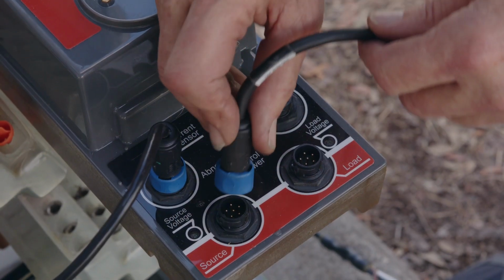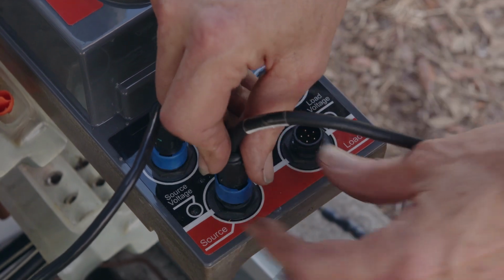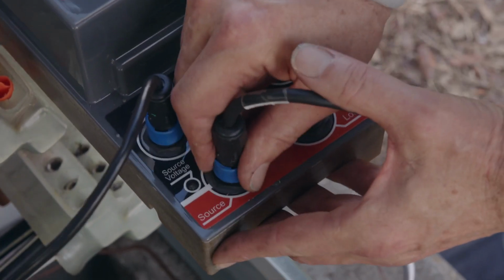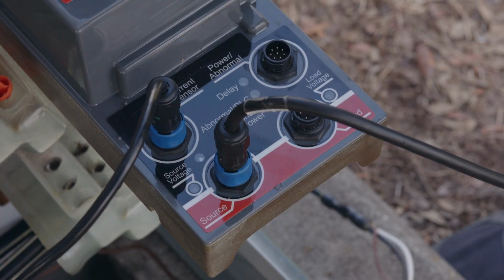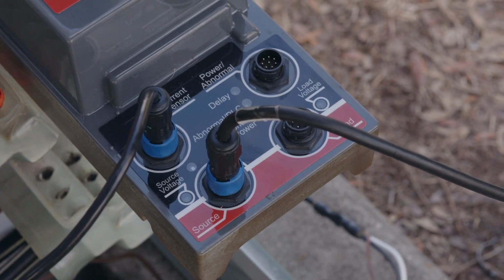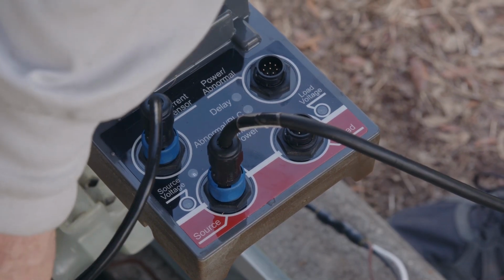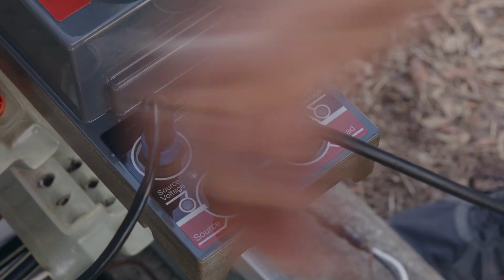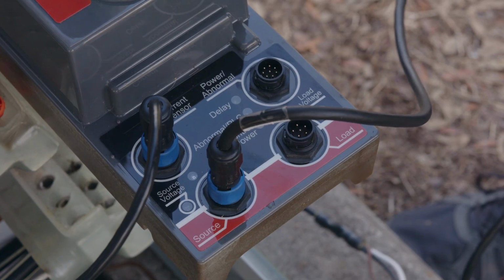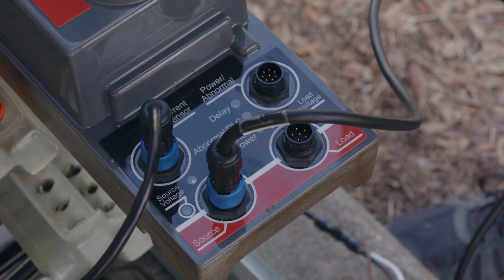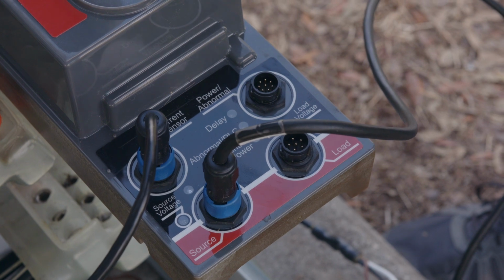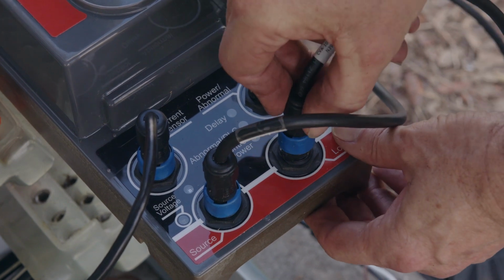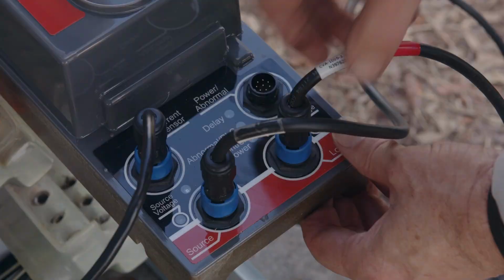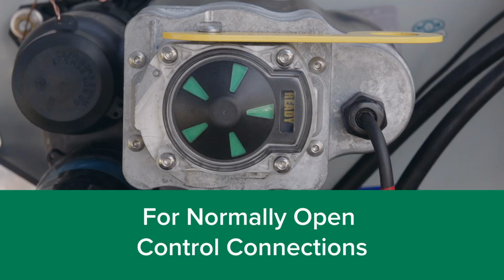Step 1. The bushing well interrupter connected to the source, utility, side cable should be connected to the 6-pin connector that is labeled Source. Step 2. The bushing well interrupter connected to the load, toward the normally open transformer, side cable should be connected to the 6-pin connector labeled Load.